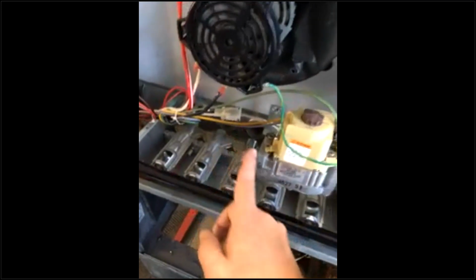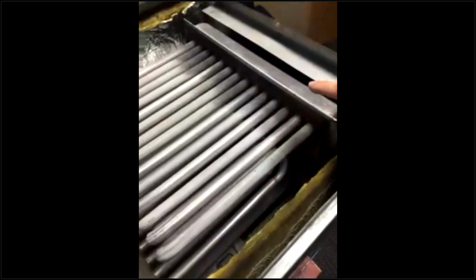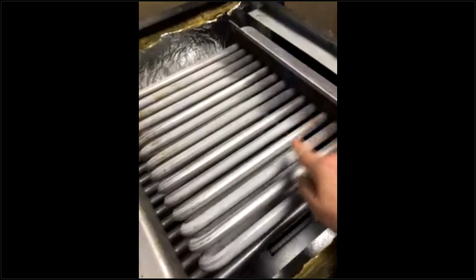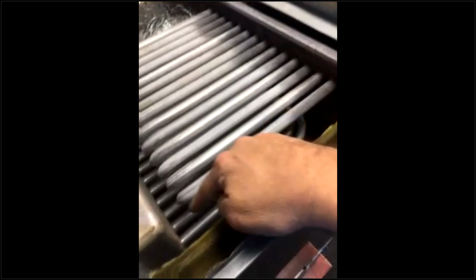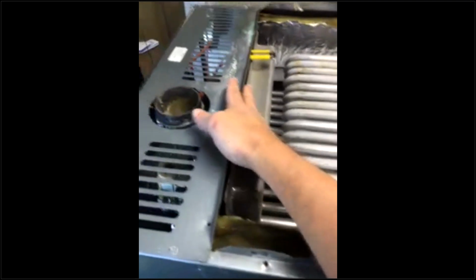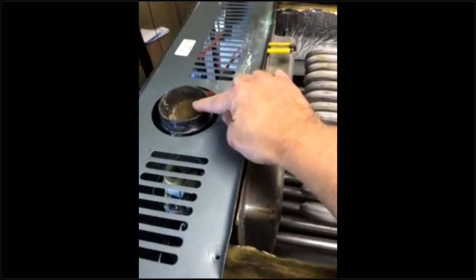Hope you all can see this. Hope this is working. So this is the heat exchanger. So right here, let's go back. So the burners are here, right? And it goes down in here, and it goes into the heat exchanger down there, which are very large pipes. You can't see them, but they're way down there. They curl up here, and they go into these smaller vent pipes, and they curl down, and they go into this one manifold here that's connected to the draft inducer fan. And it's an exhaust outside.